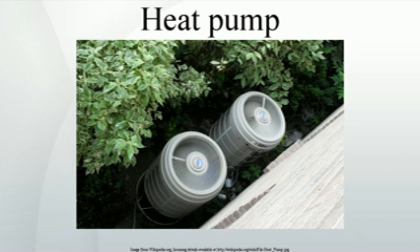Heat distribution. Heat pumps are only highly efficient when they generate heat at a low temperature differential, ideally around or below 32 degrees C, 90 degrees F. Normal steel plate radiators are not practical, because they would need to be 4 to 6 times their current size. Underfloor heating is one ideal solution.